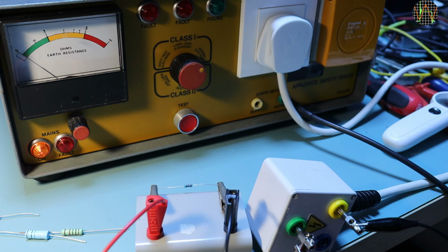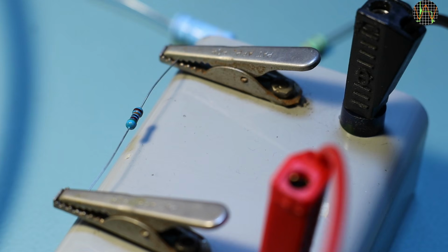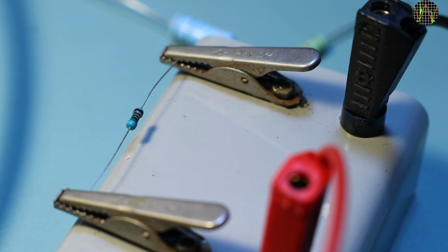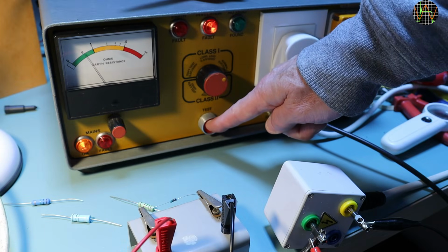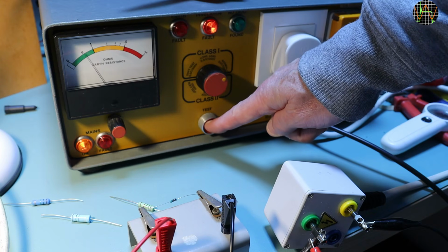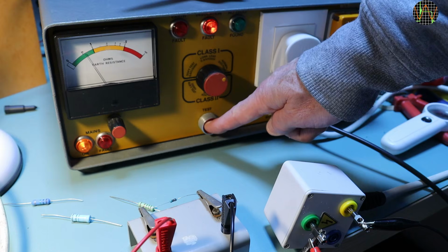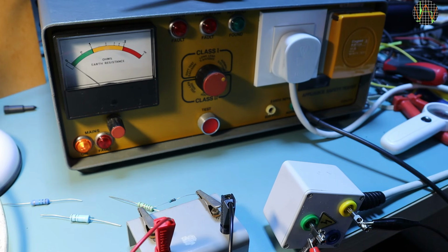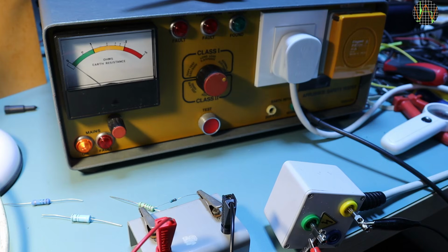Let's see, 1250 volts over 510K, that is 2.4 milliamps, times 1250 volts is slightly above 3 watts. This tiny resistor will not handle this very long. Here we go, and there is its demise. It is now failed open, but the cracks are sufficiently close to allow arcing. This is how it looks at the tester. It first passes, but while the high voltage is still present, it flashes over, causing the insulation fault to come on.